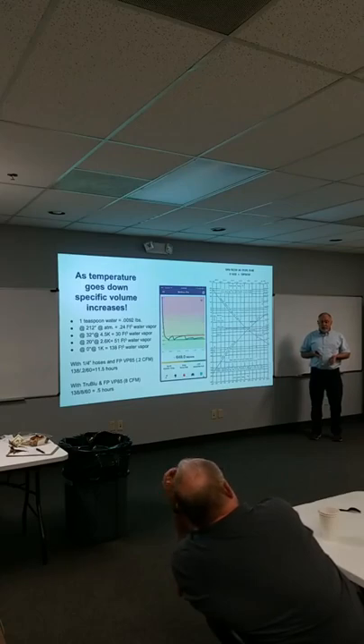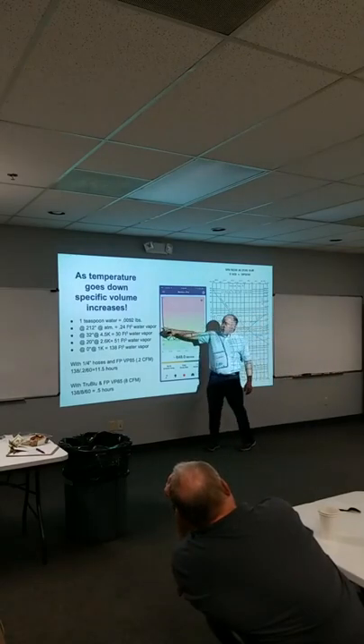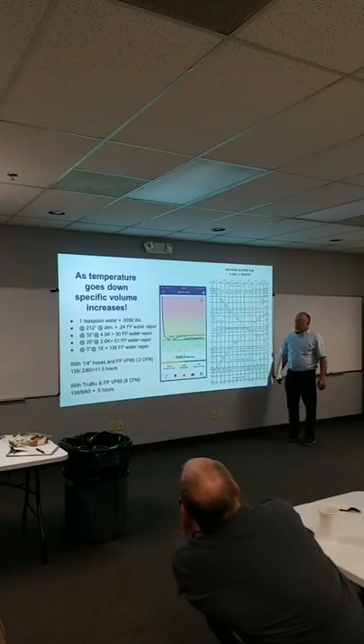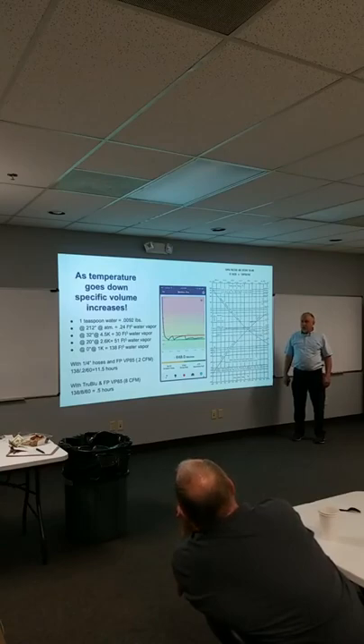Because in 1 minute, going back to the other thing I was showing you, we have 99% of the atmosphere out, right? At 20,000 microns, we've got 98.7% of the atmosphere out at that point. But all the moisture just keeps going, those bonds keep breaking. So what's happening here is if I have a teaspoon of water that weighs 0.0092 pounds, at 212 degrees and atmospheric pressure, that water would occupy 24 cubic feet of water vapor.